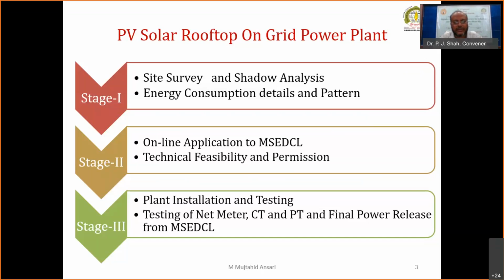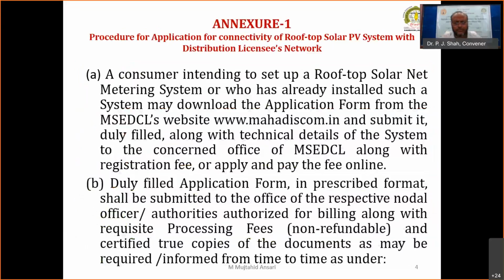The third stage is plant installation and testing. This includes testing of CT/PT whenever they need replacement, because the installed current transformers and potential transformers typically have an accuracy of 1, whereas for the solar plant, the accuracy required as per the norm is 0.5S or 0.2S depending on the capacity of the solar power plant. Finally comes the release or clearance from MSEDCL or any other state electricity board.